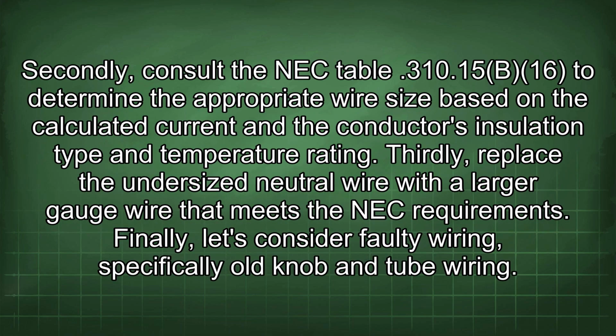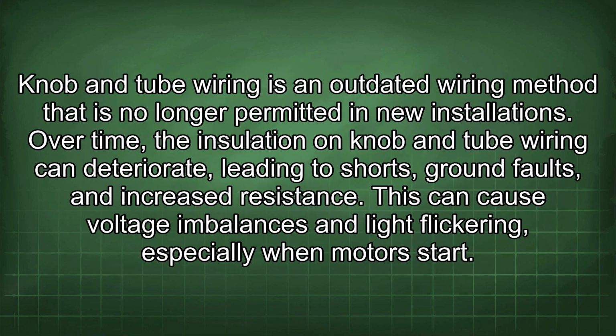Secondly, consult the NEC table 310.15(B)(16) to determine the appropriate wire size based on the calculated current and the conductor's insulation type and temperature rating. Thirdly, replace the undersized neutral wire with a larger gauge wire that meets the NEC requirements. Finally, let's consider faulty wiring, specifically old knob and tube wiring. Knob and tube wiring is an outdated wiring method that is no longer permitted in new installations. Over time, the insulation on knob and tube wiring can deteriorate, leading to shorts, ground faults, and increased resistance.